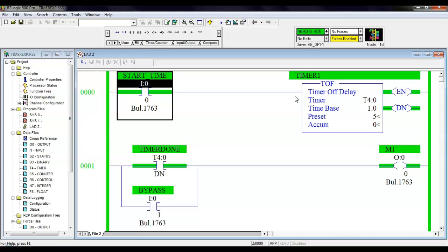So I've got the door on my car open. How long would the dome light stay on in your car if you leave the door open? When does the timer start? When you close. So what this is saying is that the timer done tells us when the timer finishes timing, but this is an off delay. So this went true instantly because the timer is not energized, it's de-energized, right? Okay. Flip it off. Motor keeps running, but now the timer's timing because I made the run go false. So an on delay timer times when the run goes true. Off delay times when the run goes what? False.